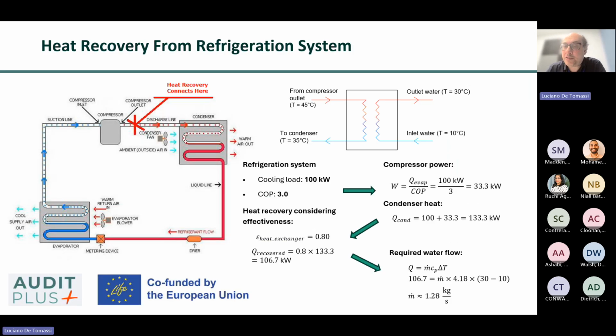Heat recovery from refrigeration systems is based on capturing the waste heat that is normally rejected at the condenser of the system and repurposing it as a useful heat source. In a conventional refrigeration cycle, heat is absorbed at low temperature in the evaporator and rejected at a higher temperature at the condenser. This rejected heat is often discharged to ambient air via air-cooled condensers or to cooling water systems. By integrating a heat exchanger into the condenser side, this otherwise wasted thermal energy can be recovered and upgraded for useful heating applications, such as space heating, hot water production, or low to medium temperature process heating.